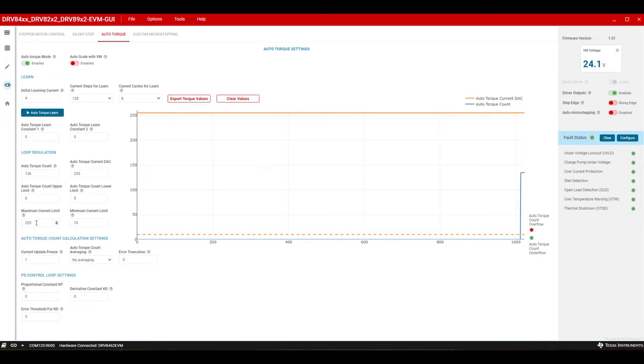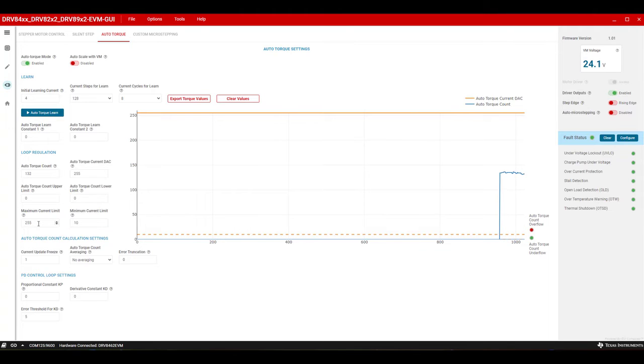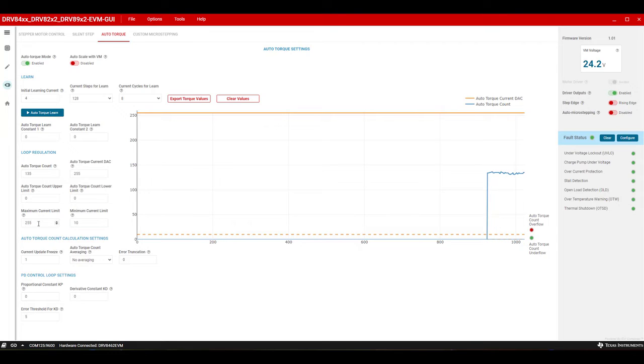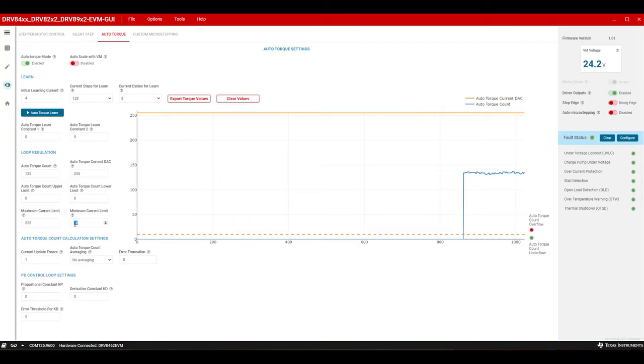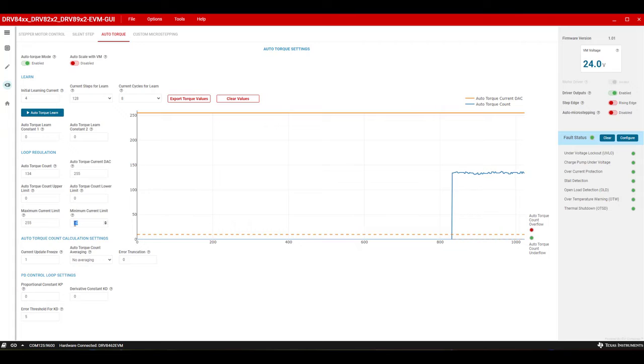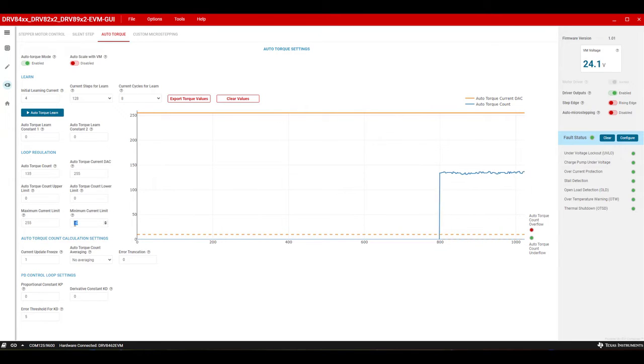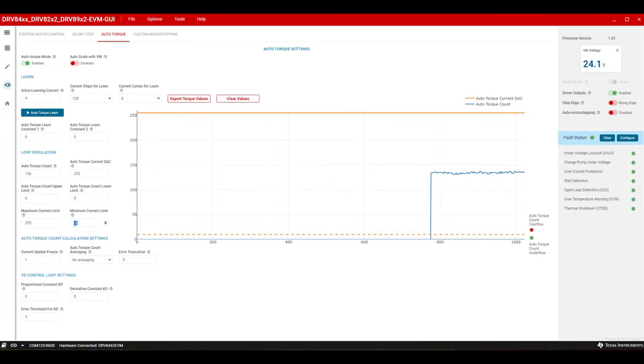Step 1: Maximum current limit setting. This can be 100% of the IFS current setting or a lower current value, depending on the application requirement. In this example, we will use 100% IFS current setting. This value will be 255, the default value. Minimum current limit setting. This is the minimum stepper current required to support the minimum load torque of the application. In this example, it is 0.5 amps. For 0.5 amps, this value will be 64.